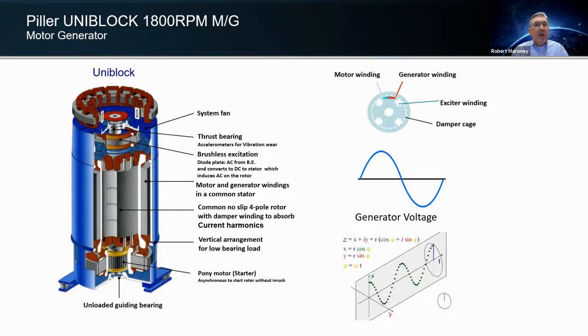Starting at the top, you heard me mention earlier that we have a single fan, and the fan sits atop the uniblock motor generator. I'll show you a picture of the UPS a little later, but that single fan is a large fan connected to this big machine that pulls air in and cools the entire UPS system, from energy storage to the DC bus to its own power electronics, and ejects it out of the system.